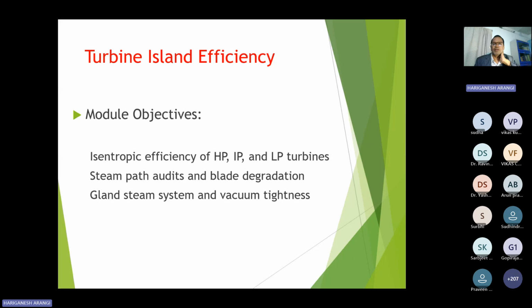Steam path audits and blade degradation, gland steam system, and vacuum tightness. That is the way to tighten the vacuum. We have to take the vacuum into the turbine, and up to 60-70% the ejector or vacuum pumps will take. For the rest, if it has to go to 100% vacuum tightness, we have to give the gland steam system. That will be low temperature steam supplied to the turbine. There will be glands on both sides of the casings. At the outside edges there will be glands, what we call labyrinth fins. In those areas we have to give the sealing steam so that vacuum losses will not be there. Because even a 1 kPa improvement in vacuum gives an improvement of 1.5% in the heat rate of the turbine.